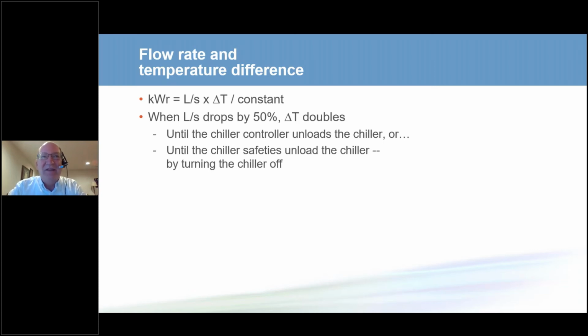In fact, in 1994, at an auto manufacturing plant, we were there, and this is exactly what happened. The chiller unit controls weren't as sophisticated, and when we attempted to turn the second chiller on, the first chiller turned off. And the owner, the auto manufacturer, said, let me understand this. We needed more cooling, so you turned all of my chillers off. That's not good, because I'm not now satisfying my manufacturing process. So in that case, we had to slow down how fast the isolation valve opens. In fact, Jim Kreutzmann, who was a consulting engineer, probably did more variable primary flow systems during his career than people who were operating at that time. He wrote articles that said the way you do this is to slow down and open that isolation valve in 2 to 3 minutes. Don't open it in 8 seconds like we did at the auto manufacturing plant. When we slowed down that valve and opened it in 3 minutes, we were able to operate the system properly.